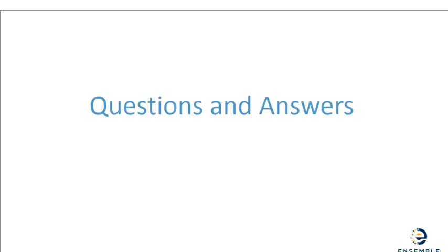There's another question, Sandeep, which I can take, which is how much historical data do you need to build a model? That's also a really good question. What we like as a minimum is 24 months of data. Kind of related to the last question, to what extent do the site conditions affect things. If a site has a lot of seasonality to it, which most sites do, we want at least 2 years of those seasons to really be able to get all those seasonal effects. In a pinch, we can use 18 months or even 12 months, but what works best is at least 24 months' worth of data.